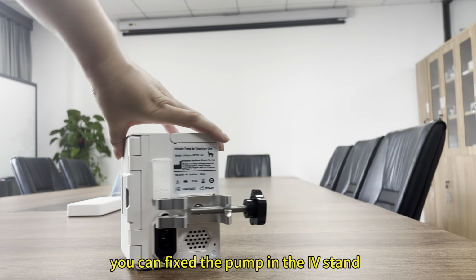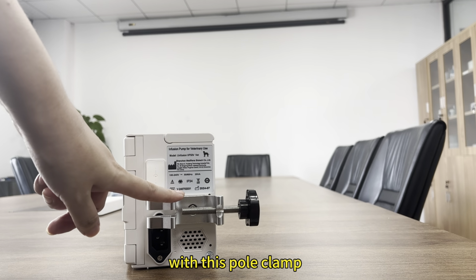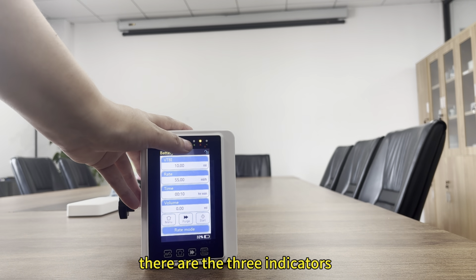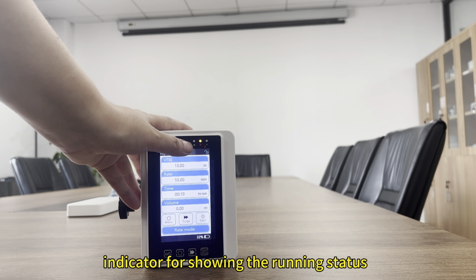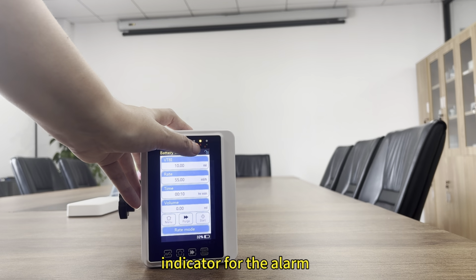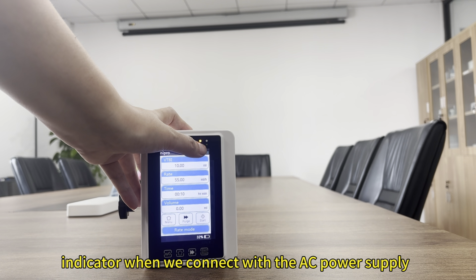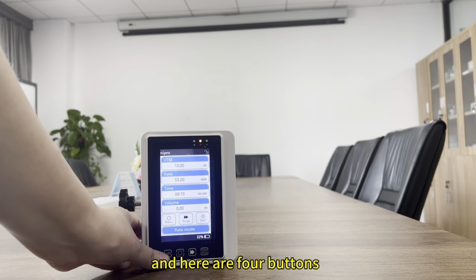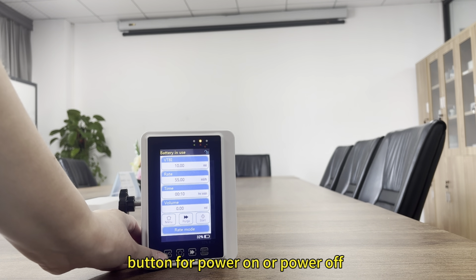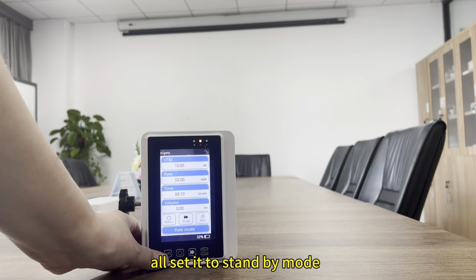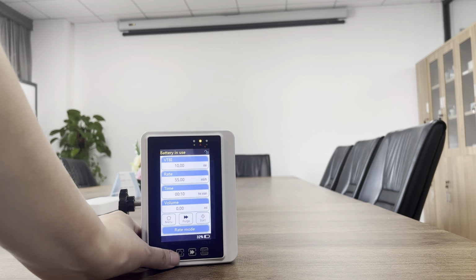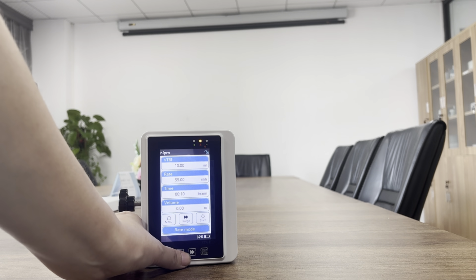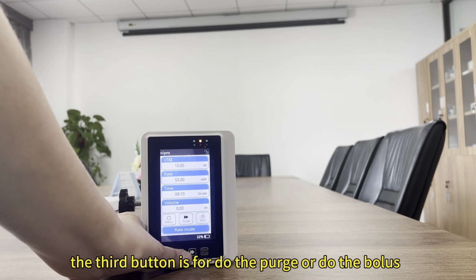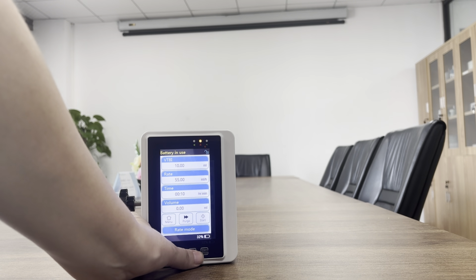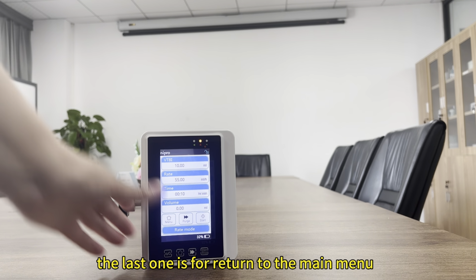You can fix the pump on the IV stand with this pole clamp. There are 3 indicators: an indicator for showing the running status, an indicator for the alarm, and an indicator for when we connect with the AC power supply. And here are 4 buttons. A button for power on or power off, or to set it to standby mode. The main menu button. The 3rd button is for doing the purge or the bolus. The last one is for returning to the main menu.